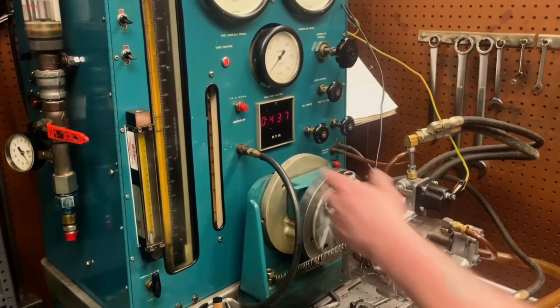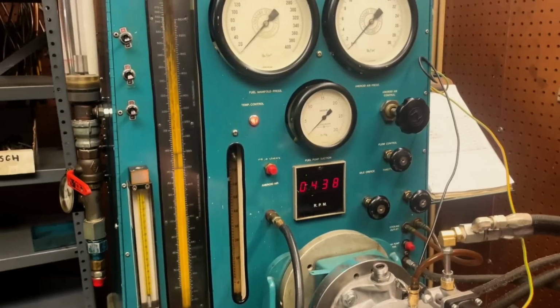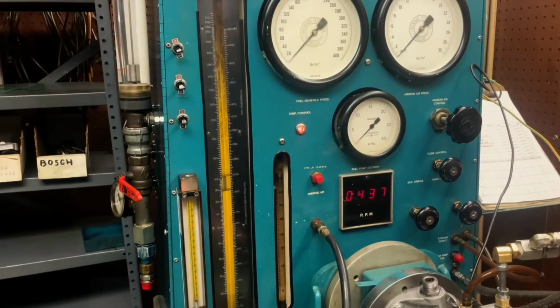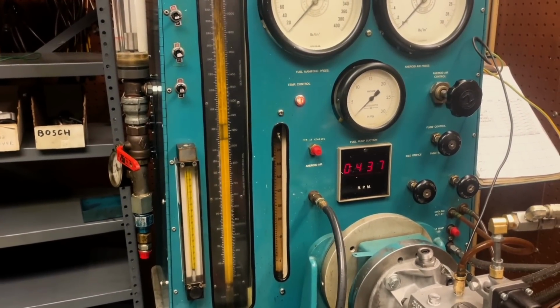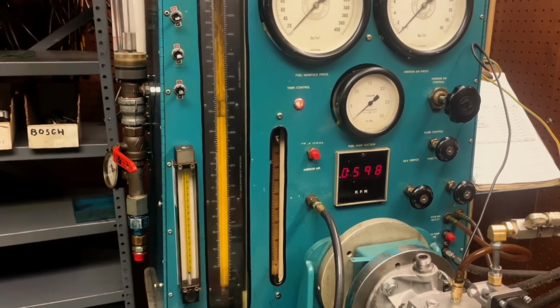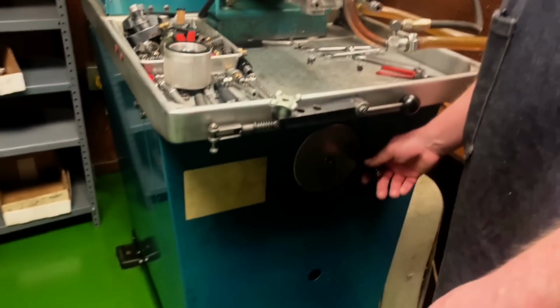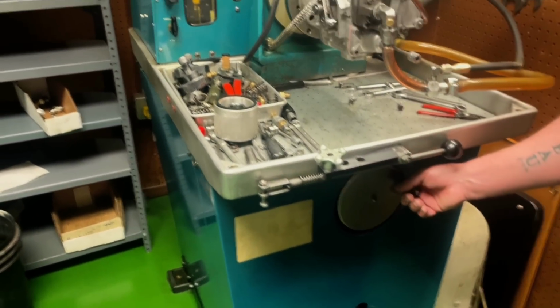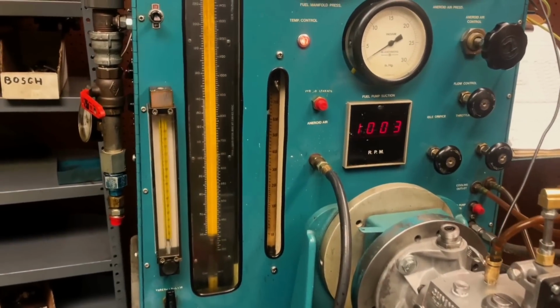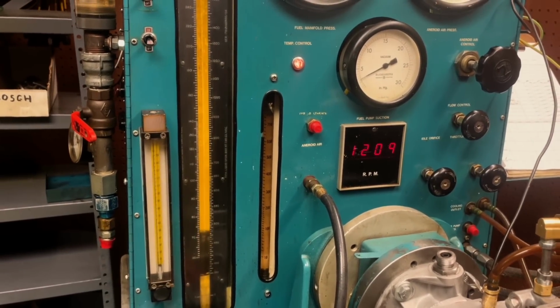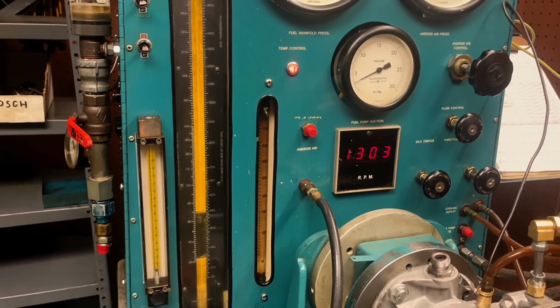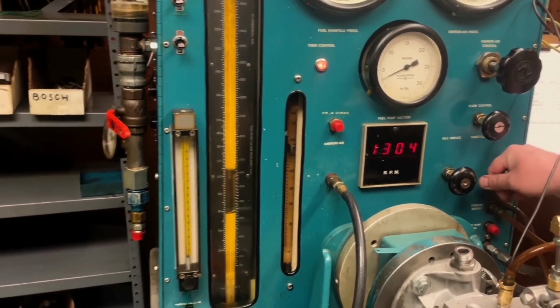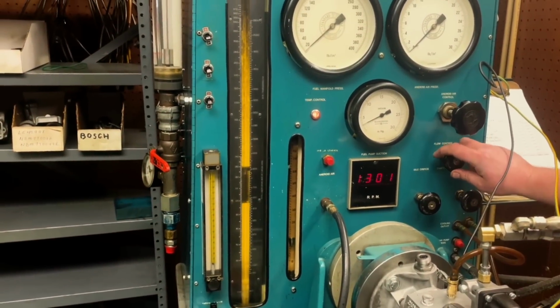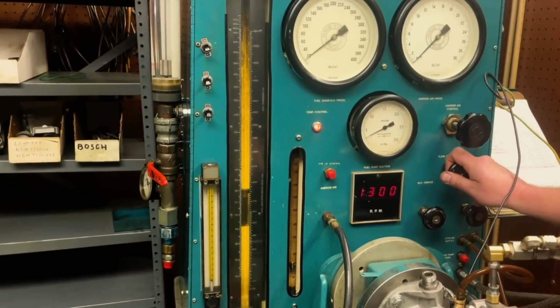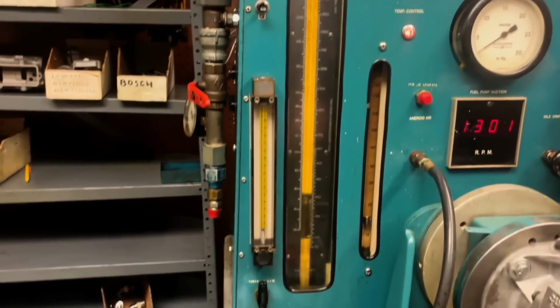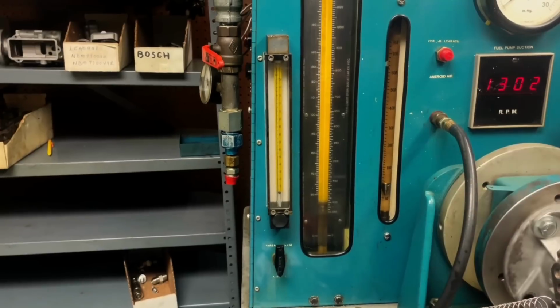When I first fired up and was trying to get all the air out of it, I had both these valves open. That's just to make sure I'm getting all the air out of it. Around to RPMs. Cranking that wheel there, picking up some RPMs. So 1300 is one of our specs. I'm going to shut this valve off and use it as a flow control valve. I'm going to try to set it, it's supposed to be a 390 to spec. This is just to give us an idea of where we're going to be, so I'm going to set it close to that.